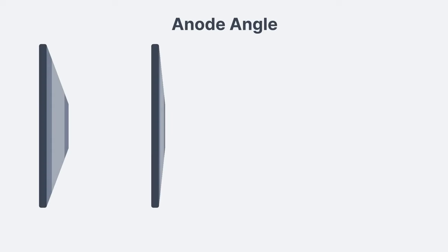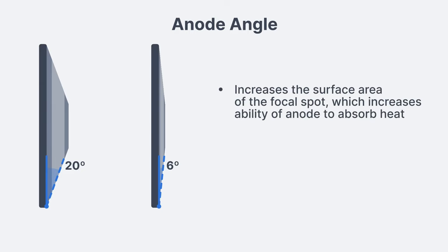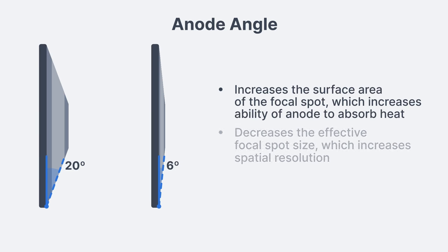Remember that the anode in general radiography is usually angled between 6 and 20 degrees. This is a good thing for two main reasons. First, the anode angle increases the surface area of the focal spot, which increases the ability of the anode to absorb heat. Additionally, the angle helps to decrease the effective focal spot size and therefore increases the spatial resolution of the radiograph.